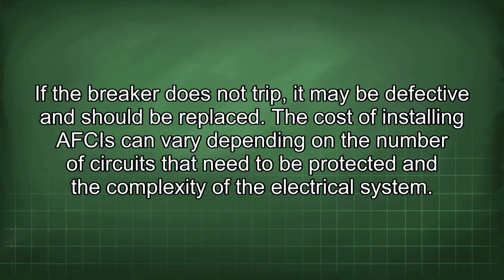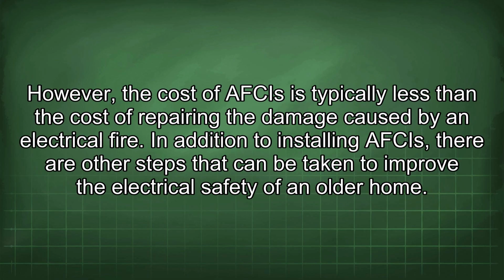If the breaker does not trip, it may be defective and should be replaced. The cost of installing AFCIs can vary depending on the number of circuits that need to be protected and the complexity of the electrical system. However, the cost of AFCIs is typically less than the cost of repairing the damage caused by an electrical fire.